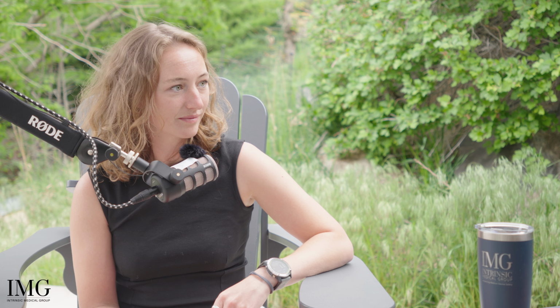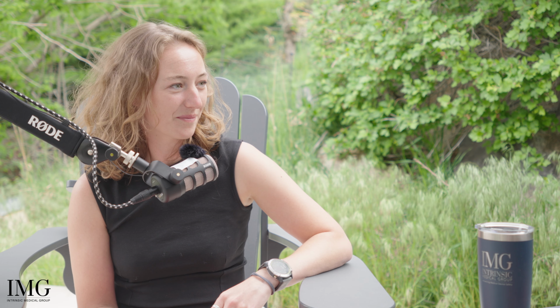And the reason it's listed is that you can buy this from a standards organization. It's sterile, it's already cut, so it's easy for the labs to use, and it's very inert and well characterized. But it very rarely is a representative control, especially when you're comparing local effects to whatever you're implanting. From my experience, 9 times out of 10, it's not the best representative material to control or compare against.